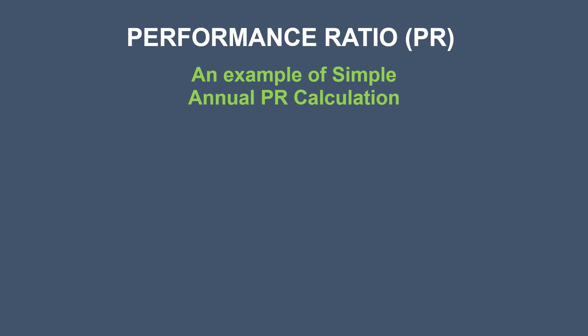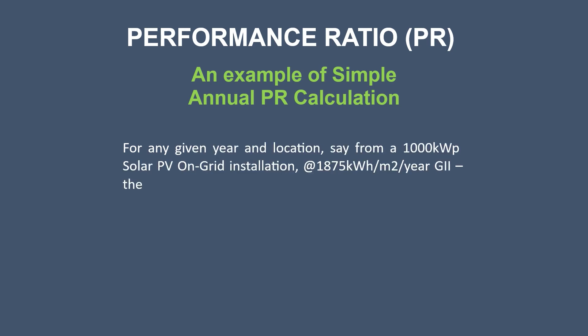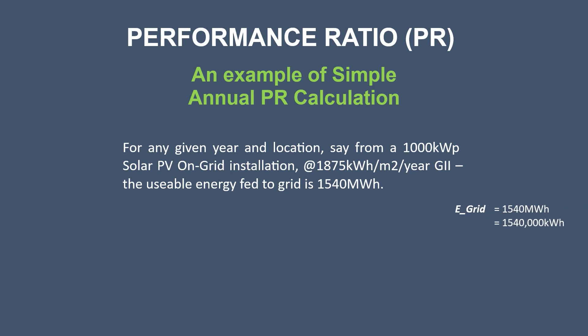Now let's look at an example of how to calculate simple annual PR with available plant operational data. For any given year and location, from a 1000 kWp solar PV on-grid installation, the annual global irradiance received at the PV plane is 1875 kWh per meter square per year, and the usable energy fed to the grid is 1540 megawatt hours. So E-grid is 1,540,000 kWh per year, GII is 1875 kWh per meter square per year, and PNOM-PV is 1000 kWp.